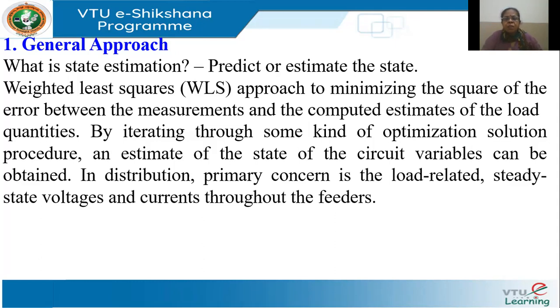Since power quality is primarily a distribution system problem, the main concern here is all load related steady state voltages and currents throughout the feeders. Okay, it is very difficult to make an estimate of harmonics, very difficult, because harmonics are very random and very dependent on the nature of the load. However, we can make an estimate for voltages.